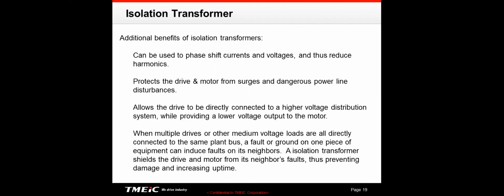We've talked about that a bit, although you'll have to go through those slides to appreciate it a little bit more. Obviously, when you get disturbances in voltage and transient voltages and so on, having that isolation transformer is very good for protecting your system. Now, it allows the drive to be directly connected to higher voltage distribution system while providing a low voltage output to the motor, and we have talked about that.